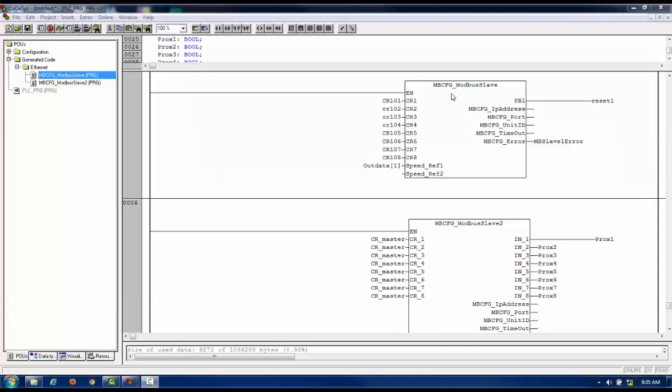So now you can see I have the program being called here. Again, like I said, I just went ahead and put in the variable names on the input-output side, writing and reading information to and from the slave device. These are your inputs over here. By the way, you get information that can be valuable, obviously here, this Modbus slave error information. We can put variables in here as far as changing input information with regards to the IP address of the device, port settings, and so forth.